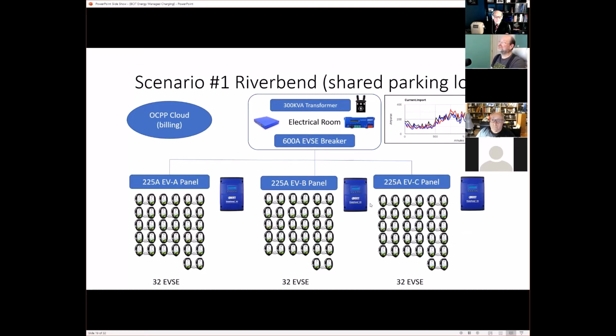In this case, if we start at the top, we have a 300 kVA transformer in the electrical room, and we monitor that with a Dent electrical meter. We can see on the side here the actual consumption from yesterday for a 24-hour period. Once these EV chargers start to use a lot of power, they will start to fill in the valley here with overnight charging. We have the peak at dinner time, and there's definitely enough power without us ever raising the peak power consumption of this building. We will monitor the transformer to make sure it never exceeds its kVA limit. We have our local controller in the electrical room, and a 600 amp breaker feeding basically 100 EVSEs.